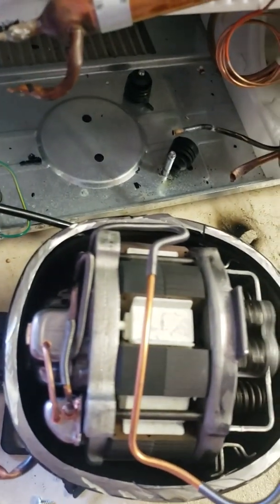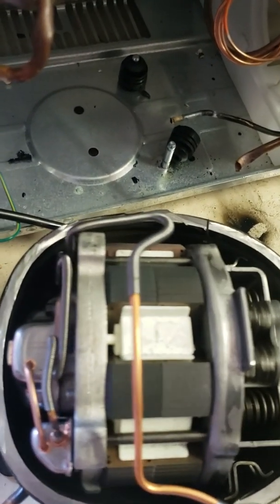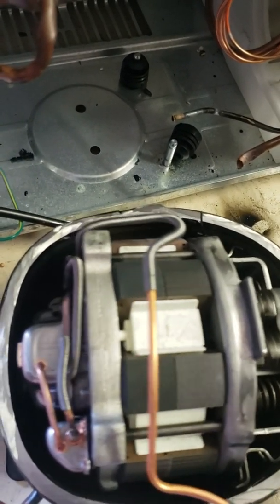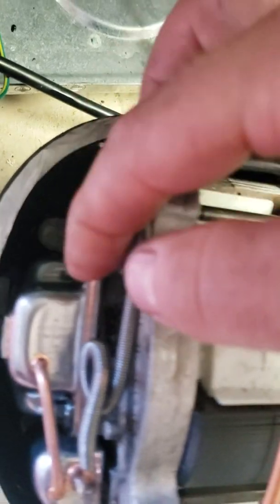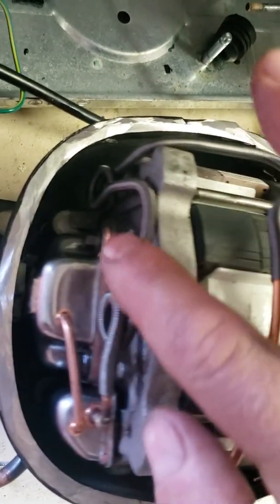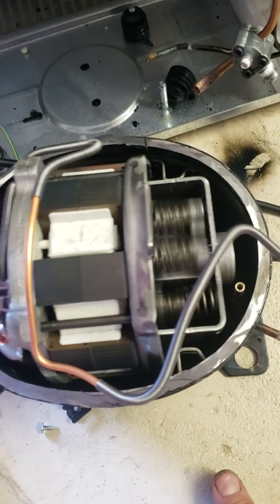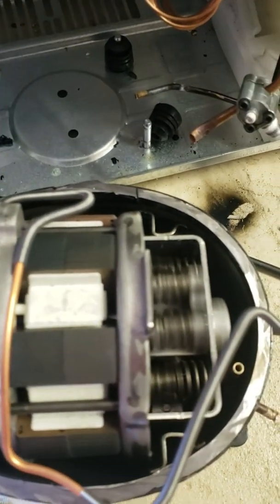This whole thing is vibrating - that line connects here but everything vibrates. I wouldn't be surprised if these lines would fail, because there's a lot more vibration than the rotary compressor.